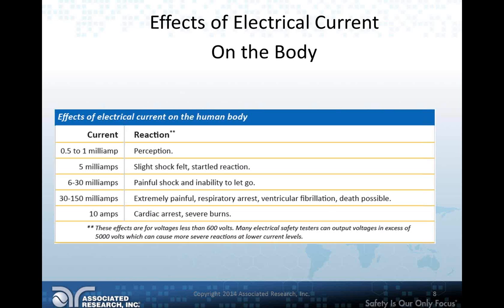Many electrical safety testers out there, ours included, can output voltages in excess of 5,000 volts. Some of ours do more - we can go up to 20,000 volts AC and DC. The point is that at much higher voltages, these numbers would be reduced. Those effects at high voltages haven't been studied in depth, which is why we haven't provided those numbers, but I think these numbers provide a really good base of what you need to look out for.